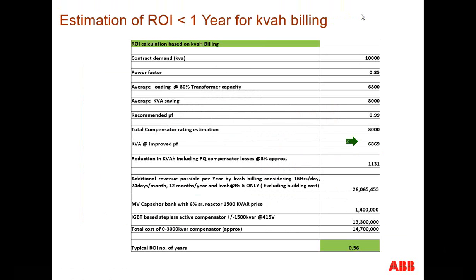This is calculated considering that the kVA contract demand is at 0.85 power factor and 80% loading on the transformer. So the average kVA is coming around 8000. If we recommend going for 0.99 power factor, the total compensation required is about 3000 kVAr, with which the improved power factor gives about 6869, that is 6869 as against 8000. So we get a reduction in kVA of about 1131.